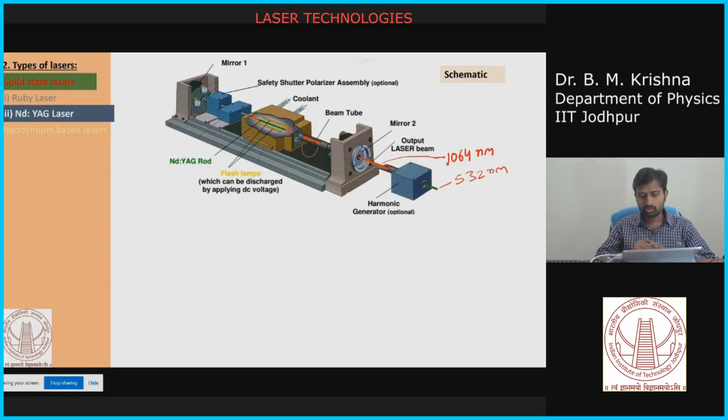Okay, so the nonlinear crystal should be maintained at certain humidity conditions and certain temperatures, and at different angles. When you tune the angle, the percentage of conversion will change. You don't expect the conversion efficiency to be 100%. In principle, you cannot convert all the IR light, all the 1064 nanometer, into 532 nanometer. There is always a certain conversion threshold or conversion efficiency of the crystal.